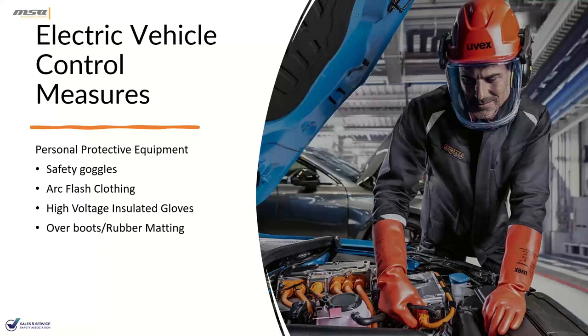Lastly, I want to talk about over boots and rubber matting. When it comes to electricity, it wants to get from the battery to the ground, and the human body can be used to conduct this energy. By insulating the operator's hands and feet, the energy cannot reach the ground, protecting the operator from fatal shock. Again, 1,000-volt rubber matting on the floor and high voltage over boots can provide this protection to the worker.